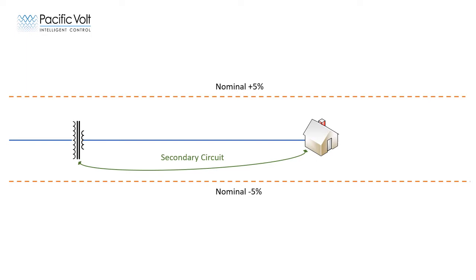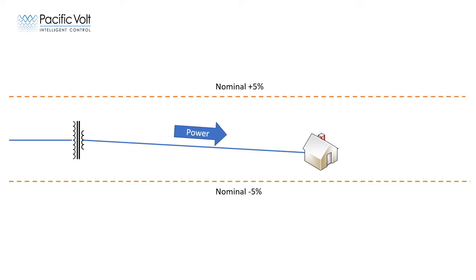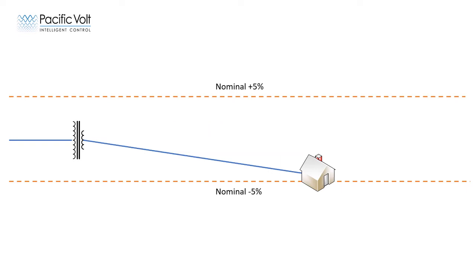Just like on the medium voltage feeder, the impedance of the transformer and the secondary circuit conductors cause the voltage to drop in proportion to the amount of power being consumed. The amount the voltage drops depends on the amount of power being consumed and the impedance of the secondary circuit. Additionally, the longer the secondary circuit is, the higher its impedance is, which causes the voltage to drop more.